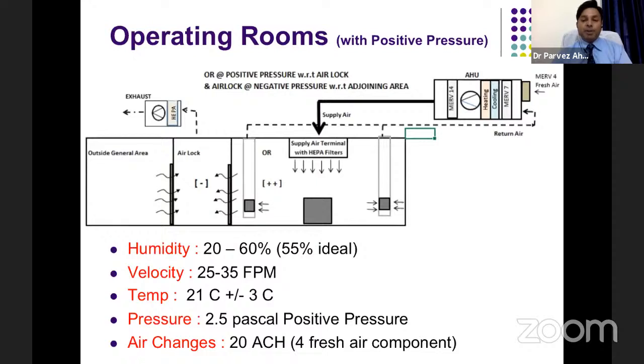2.5 pascal positive pressure is to be maintained, and a minimum of 20 air changes should be maintained, with a component of 4 fresh air changes. So this is the model of the positive pressure operating room with use of HVAC and laminar flow AHU. This is the highly recommended model.